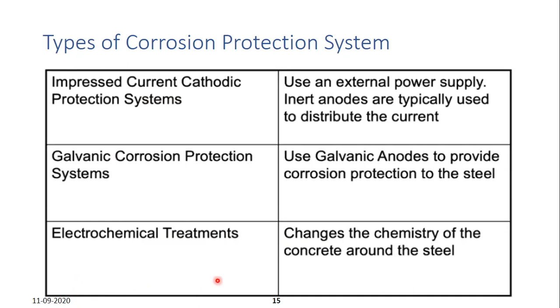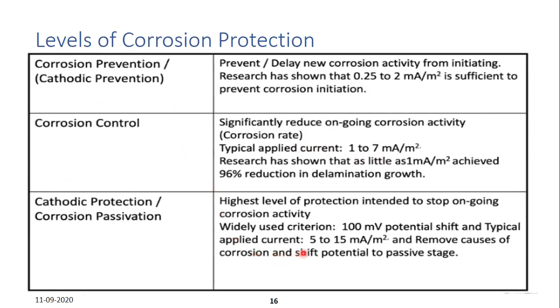Level of corrosion. First, if corrosion is at the initiation level, you pass a little bit of current, 0.25 to 2 milliampere per meter square. If corrosion is ongoing, you pass a current level of 1 to 7 milliampere per meter square and protect the whole structure. If corrosion is global, you pass a high current, 5 to 15 milliampere per meter square.